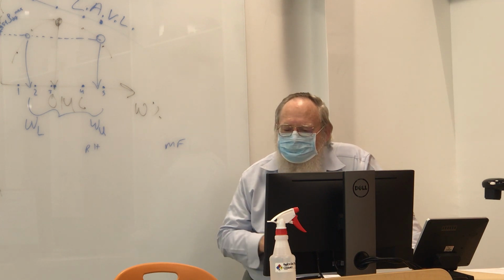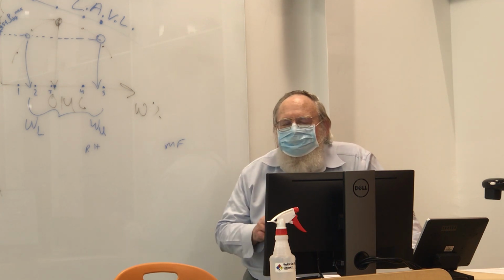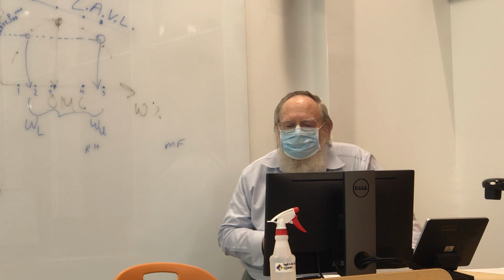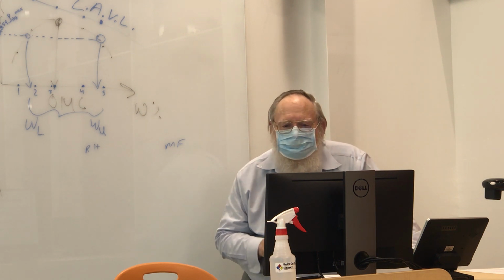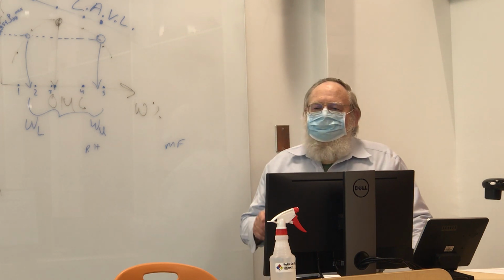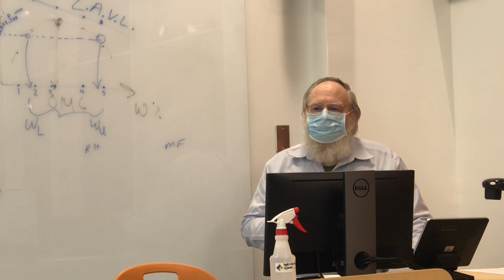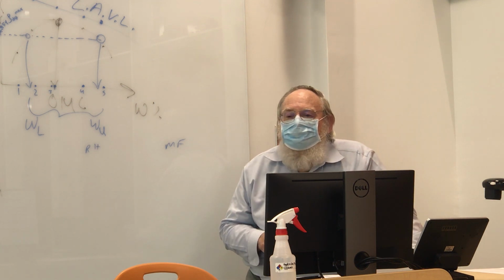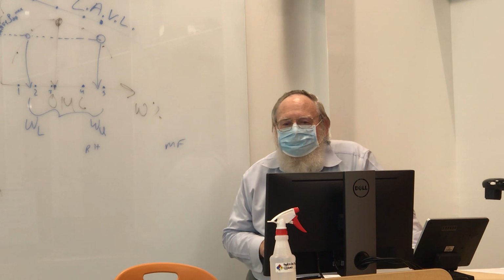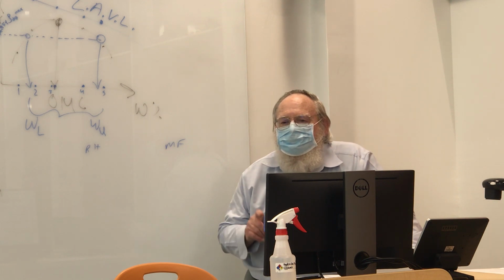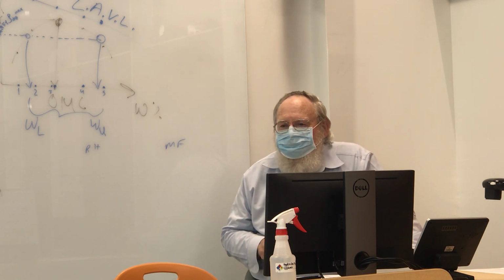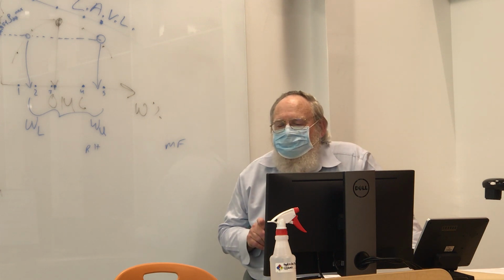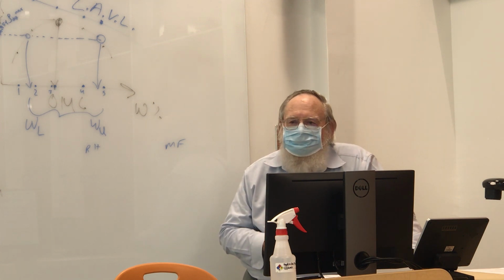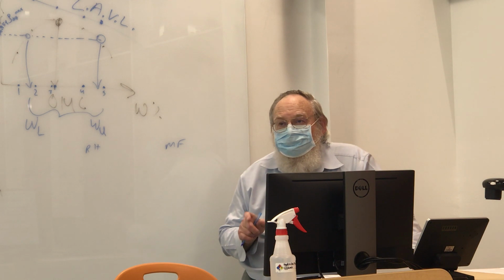And the guy said, yeah, breaker's open. But my friend thought about it for a while and he said, you know what, I'm going to double check. And so he did. Took a voltmeter, went up to the pump leads, and what he found was that even though the breaker was open, there was 120 volts on the pump leads because somebody had wired the breaker incorrectly and put it on the neutral side.